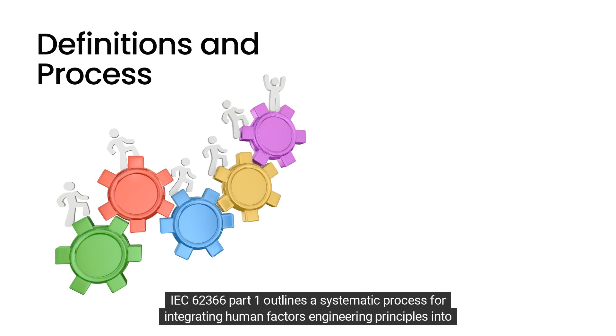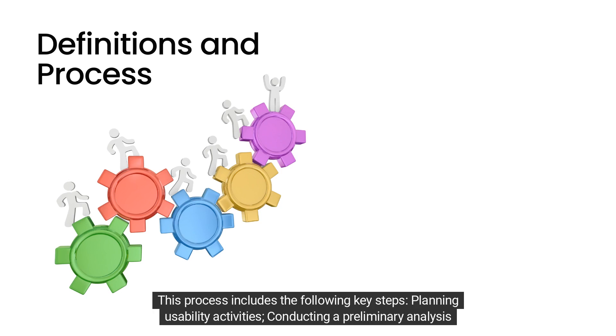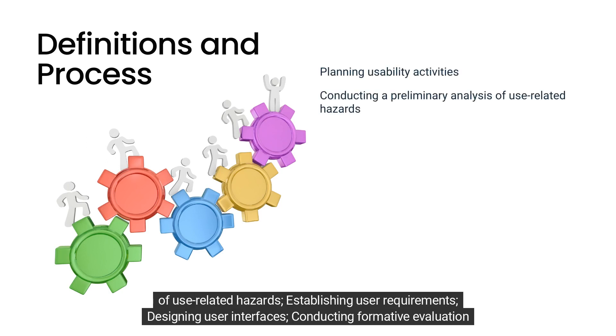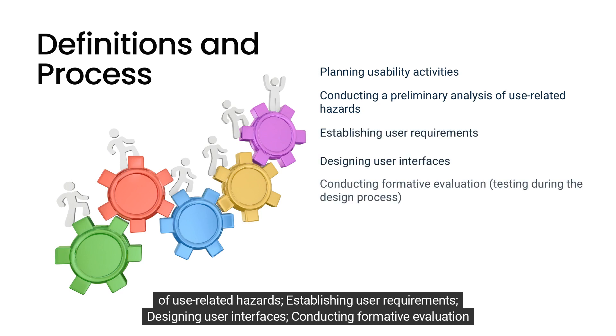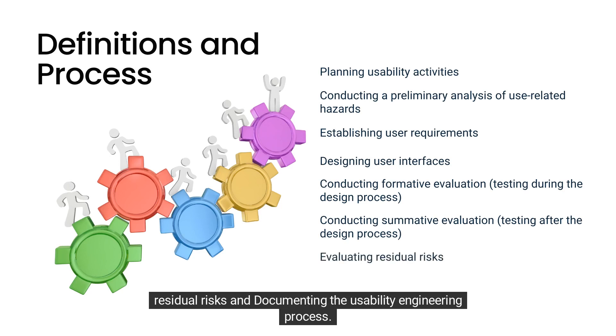IEC 62366 Part 1 outlines a systematic process for integrating human factors engineering principles into the design and development of medical devices. This process includes the following key steps: planning usability activities, conducting a preliminary analysis of use-related hazards, establishing user requirements, designing user interfaces, conducting formative evaluation and testing during the design process, conducting summative evaluation and testing after the design process, and evaluating residual risks and documenting the usability engineering process.